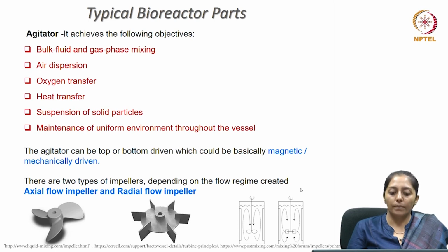Agitators can be top or bottom driven. Generally, you will find magnetically driven impellers or mechanically driven impellers. These days, mostly magnetically driven impellers are used because they can avoid contamination due to leakage in the shaft seals.